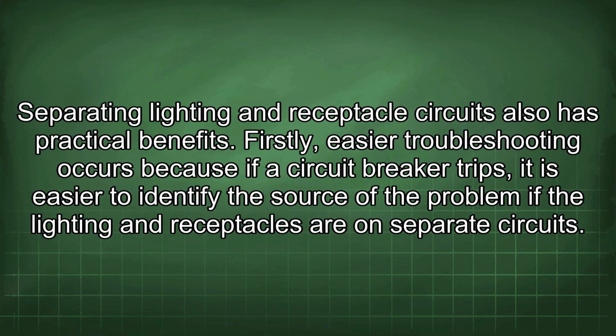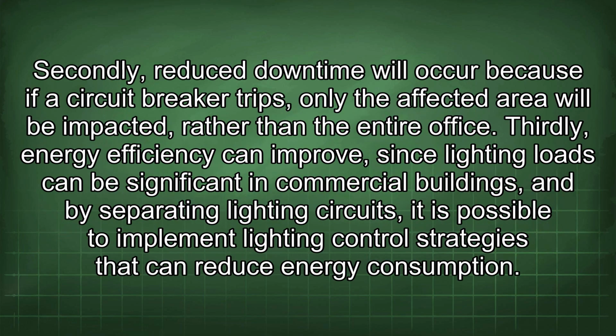Separating lighting and receptacle circuits also has practical benefits. Firstly, easier troubleshooting occurs because if a circuit breaker trips, it is easier to identify the source of the problem if the lighting and receptacles are on separate circuits. Secondly, reduced downtime will occur because if a circuit breaker trips, only the affected area will be impacted, rather than the entire office. Thirdly, energy efficiency can improve, since lighting loads can be significant in commercial buildings, and by separating lighting circuits, it is possible to implement lighting control strategies that can reduce energy consumption.